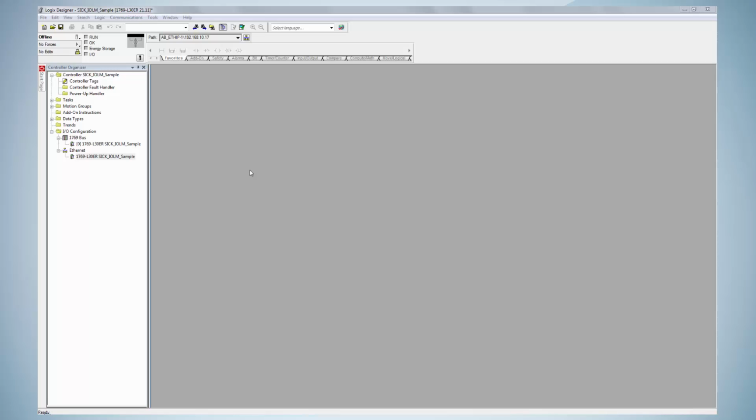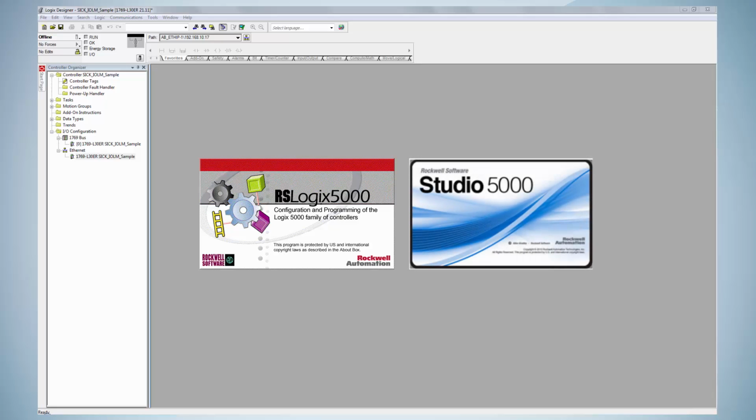When having entered the IP address into the device, the hardware configuration will be continued in the RS Logix software or Logix Designer. First of all, the IO-Link Master needs to be implemented into the PLC environment. For this purpose, it is necessary to switch to the PLC's Ethernet interface. There are two ways how to implement the IO-Link Master into the Ethernet IP environment. First, we will show the way that is possible for all RS Logix software using a generic module, and then the way that is possible from version 20 onwards only using an EDS file.